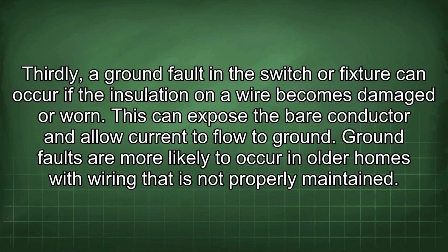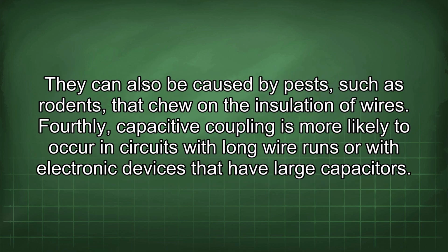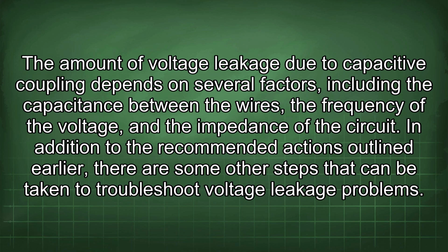Thirdly, a ground fault in the switch or fixture can occur if the insulation on a wire becomes damaged or worn. This can expose the bare conductor and allow current to flow to ground. Ground faults are more likely to occur in older homes with wiring that is not properly maintained. They can also be caused by pests, such as rodents, that chew on the insulation of wires. Fourthly, capacitive coupling is more likely to occur in circuits with long wire runs or with electronic devices that have large capacitors. The amount of voltage leakage due to capacitive coupling depends on several factors, including the capacitance between the wires, the frequency of the voltage, and the impedance of the circuit.